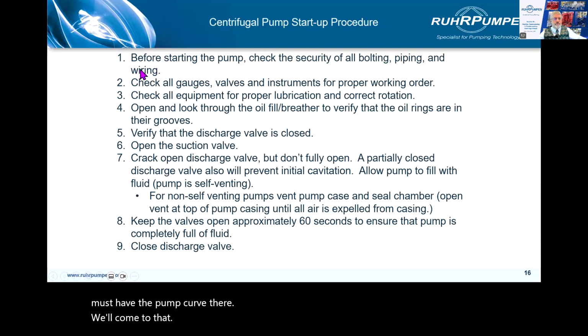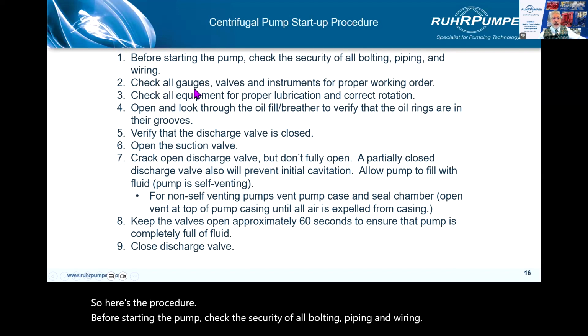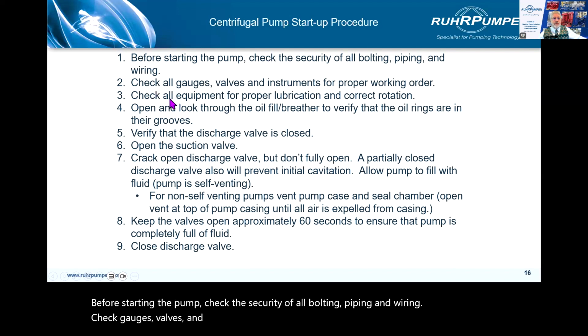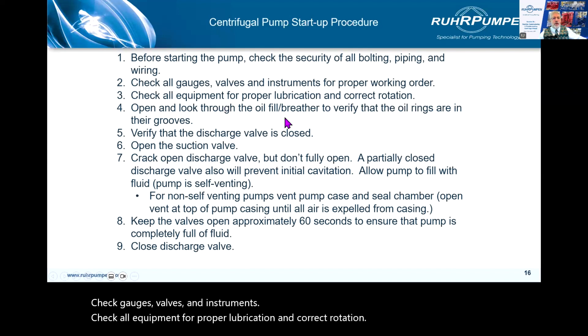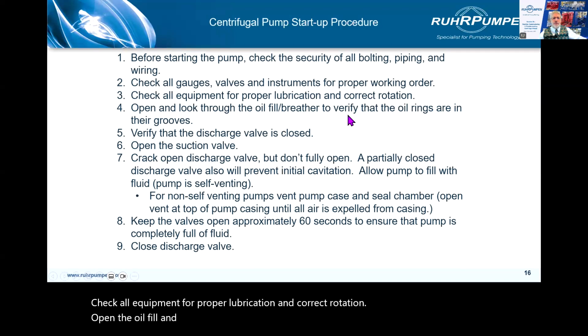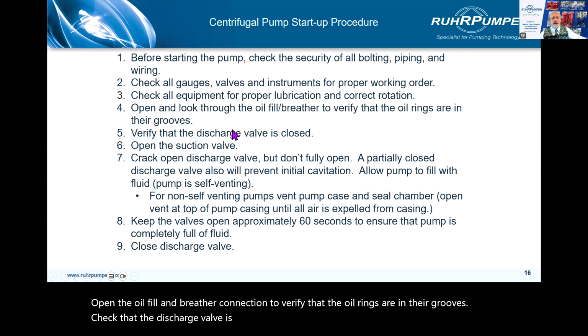So here's the procedure. Before starting the pump, check the security of all bolting, piping, and wiring. Check gauges, valves, and instruments. Check all equipment for proper lubrication and correct rotation. Open the oil fill and breather connection to verify that the oil rings are in their grooves. Check that the discharge valve is closed. Then open the suction valve.